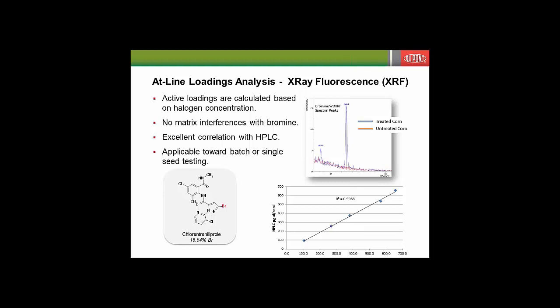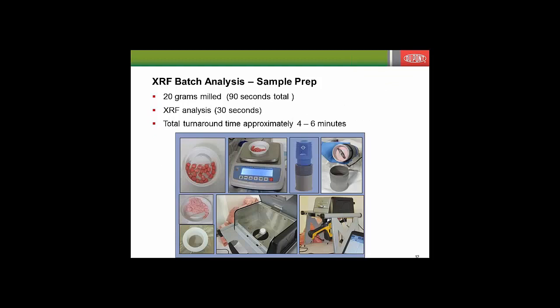And again, the intent is that, say if you are at a remote plant that does not have a traditional analytical lab, a portable XRF spectrometer could be used to measure the pesticides right there at line. The prep does involve some pre-processing.